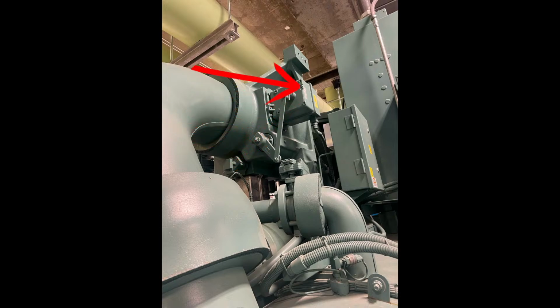So if this mechanical linkage is not put in just right, then you could be causing an overcurrent issue at startup. That'll probably be the primary symptom that you're going to deal with. In addition, it's going to have a hard time unloading as much as it needs to when it needs to close the vanes, stuff like that. So just be aware of that in the process.